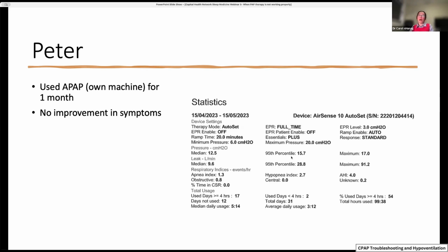The pressure required is about 15.7 or less, 95% of the time. And he has a little bit more leak compared to Penny. So his mask is leaking at 28.8 liters per minute or more about 5% of the time. But the median is, again, quite reasonable. And the machine says the residual apnea-hypopnea index is 4.